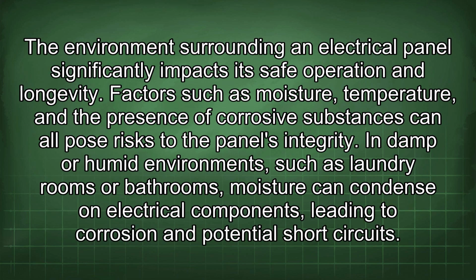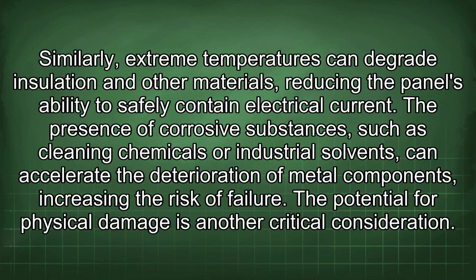The environment surrounding an electrical panel significantly impacts its safe operation and longevity. Factors such as moisture, temperature, and the presence of corrosive substances can all pose risks to the panel's integrity. In damp or humid environments, such as laundry rooms or bathrooms, moisture can condense on electrical components, leading to corrosion and potential short circuits. Similarly, extreme temperatures can degrade insulation and other materials, reducing the panel's ability to safely contain electrical current. The presence of corrosive substances such as cleaning chemicals or industrial solvents can accelerate the deterioration of metal components, increasing the risk of failure.